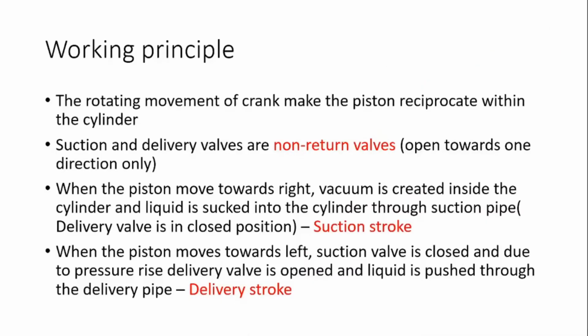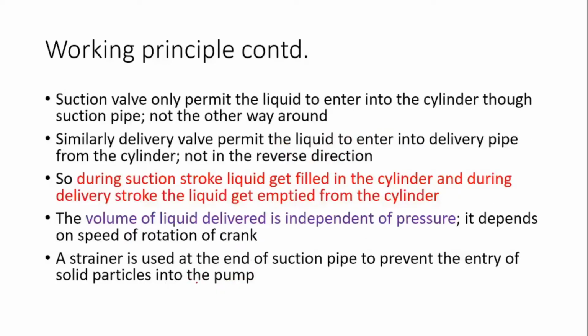Now let's review this working principle again. We have two non-return valves, suction valve and delivery valve. During the suction stroke, when the piston moves towards the right, vacuum is created and liquid is sucked into the cylinder through the suction pipe. During the delivery stroke, the piston moves towards the left, the suction valve is closed, and due to the high pressure, the delivery valve is opened and the liquid flows through the delivery pipe.